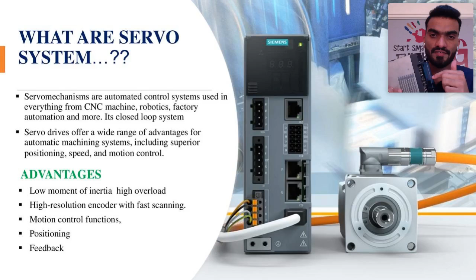It's a combination, as I said, a drive and motor combination. Whenever you take a servo system, it is both motor and drive together. We call it a servo system because each motor should talk with the same brand of drive, and sometimes the model should also be the same. You connect your power here, and the same power output is given to the motor through this drive only; you don't connect any external power to the motor. Through the communication port, you connect to the motor and take feedback from it. Your drive receives all the feedback and sends it to HMIs and SCADA, so you can see what's happening with the servo motor.